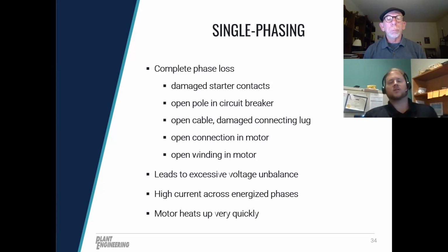Single phasing leads to extremely high current imbalance, just generally high current across the energized phases. You won't have any current across the single phased line. And what's that going to do? It's going to cause your motor to really heat up very quickly. If a motor is single phased for very long, it's going to short circuit.